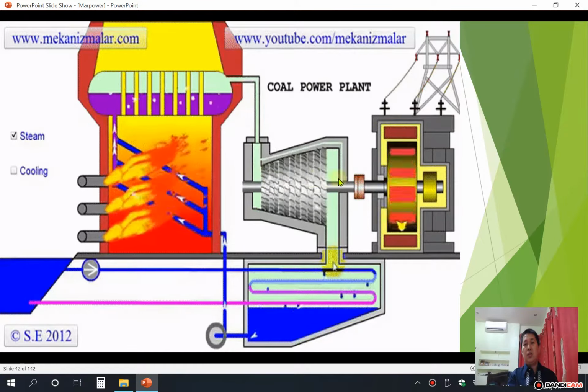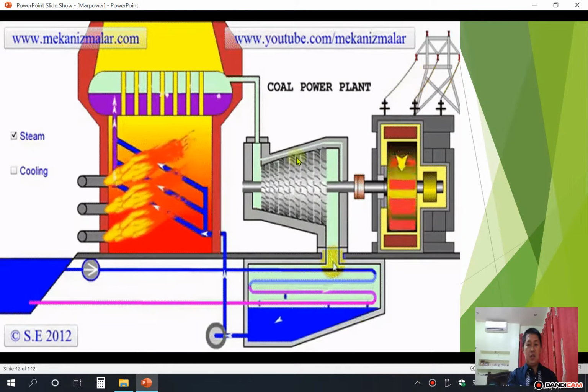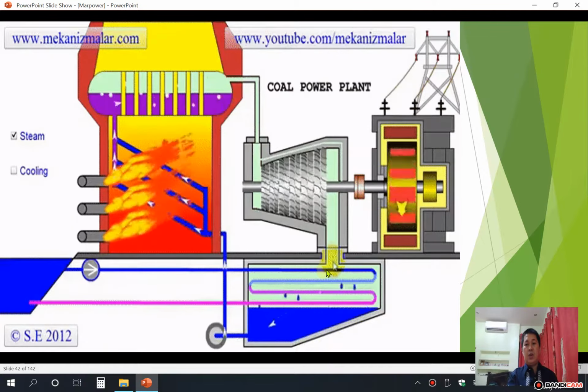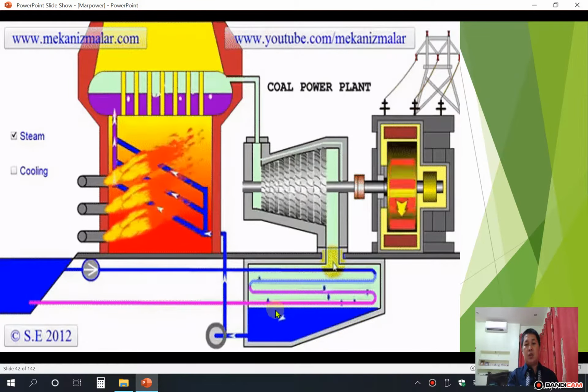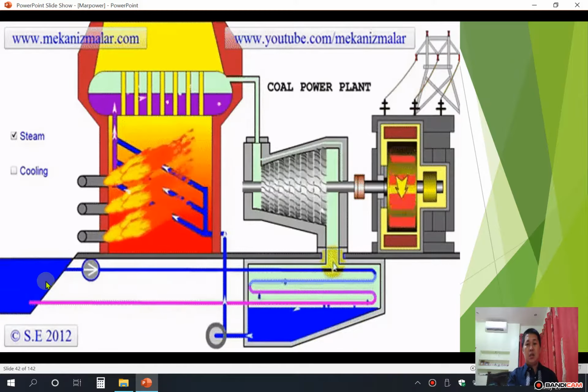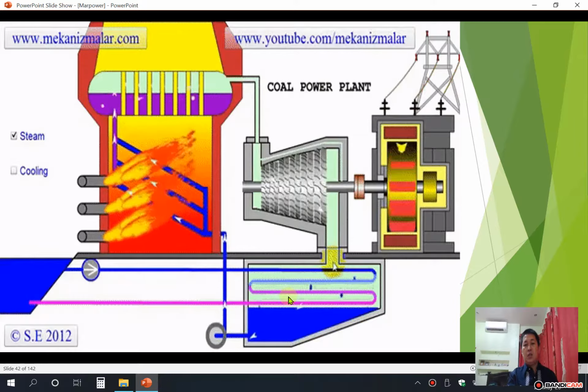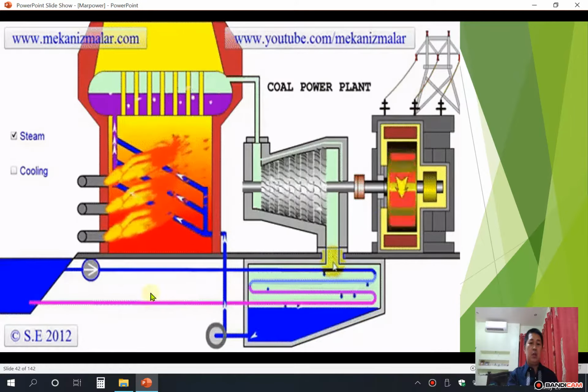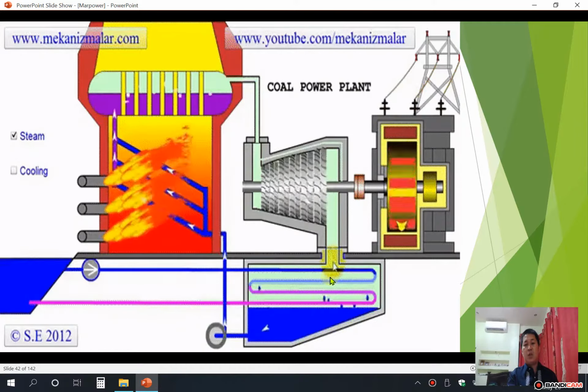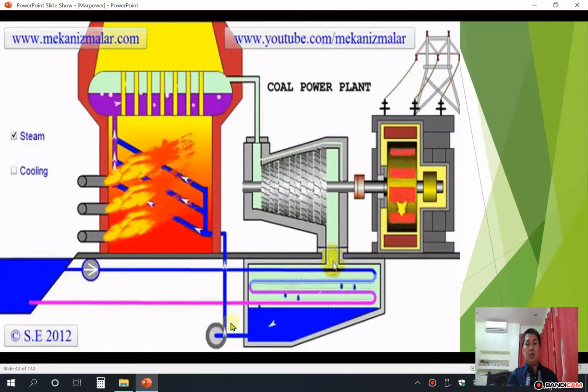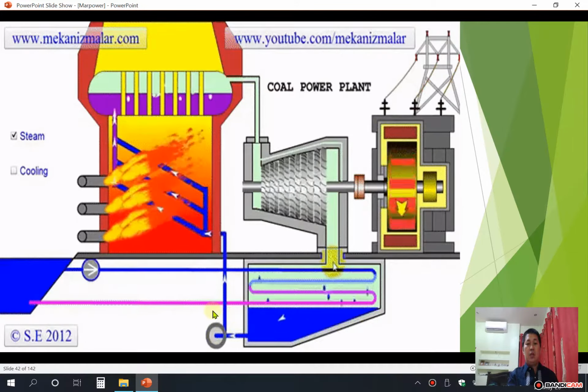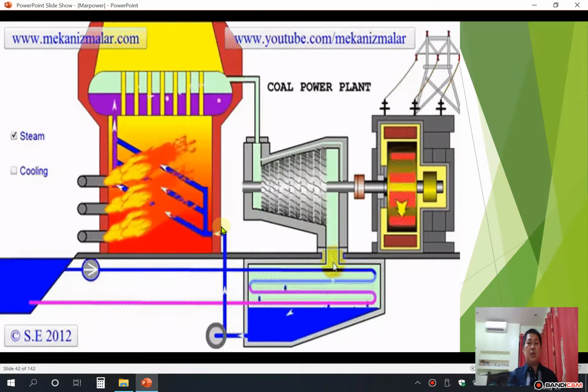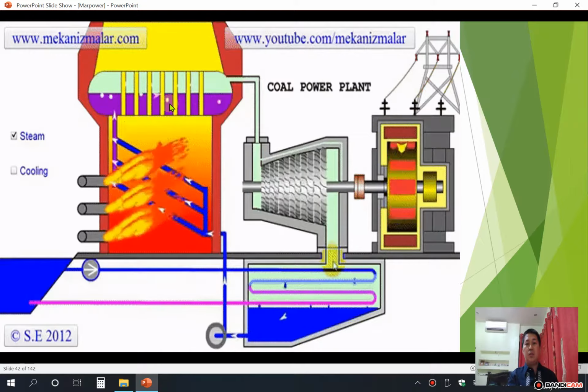turn the turbine, and the turbine is coupled to your alternator and you are producing electricity. The steam used in the turbine will exhaust to the main condenser, and you see seawater here. There is a heat rejection here, and this steam will be converted again into fresh water. It will be sucked by the feed pump and delivered again to your boiler. It becomes boiler water again. So this is the basic steam cycle.